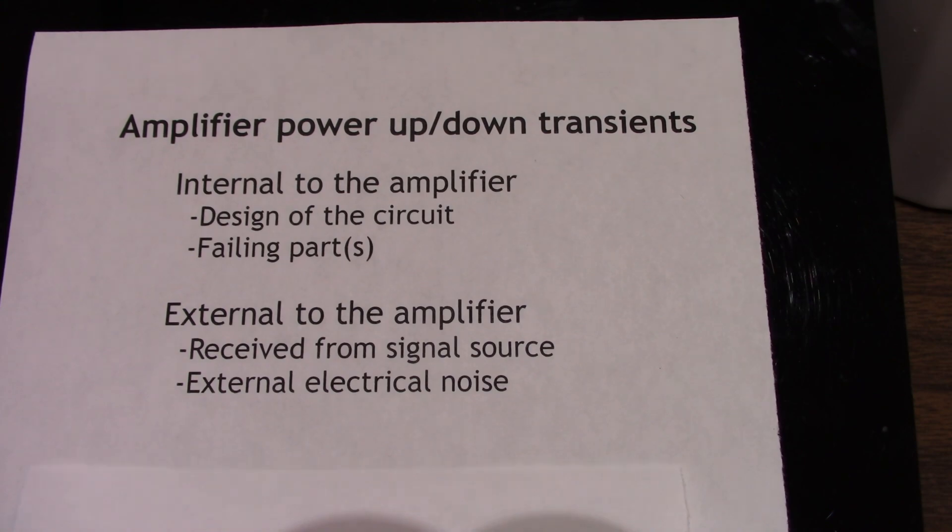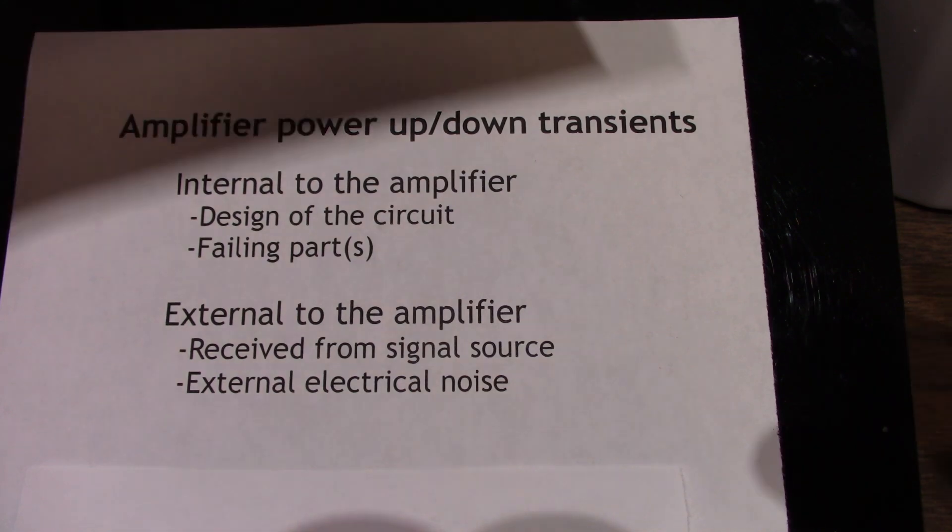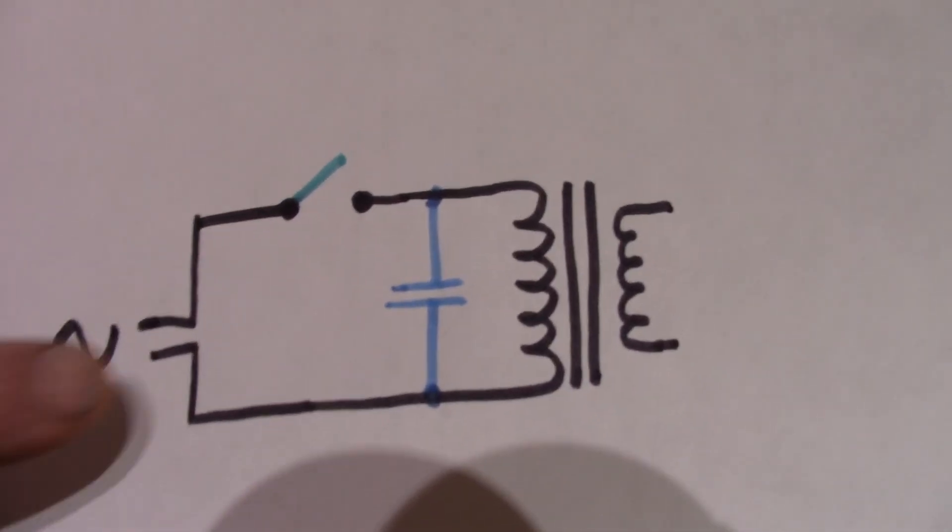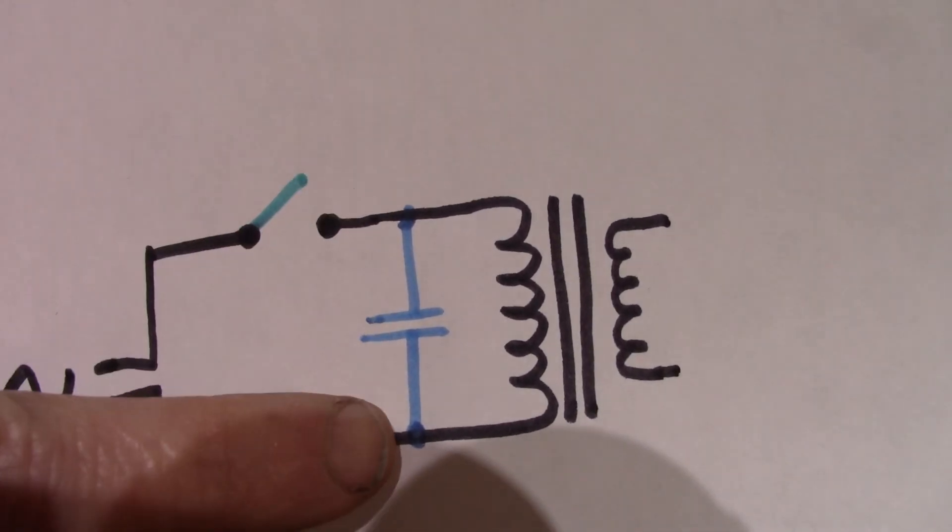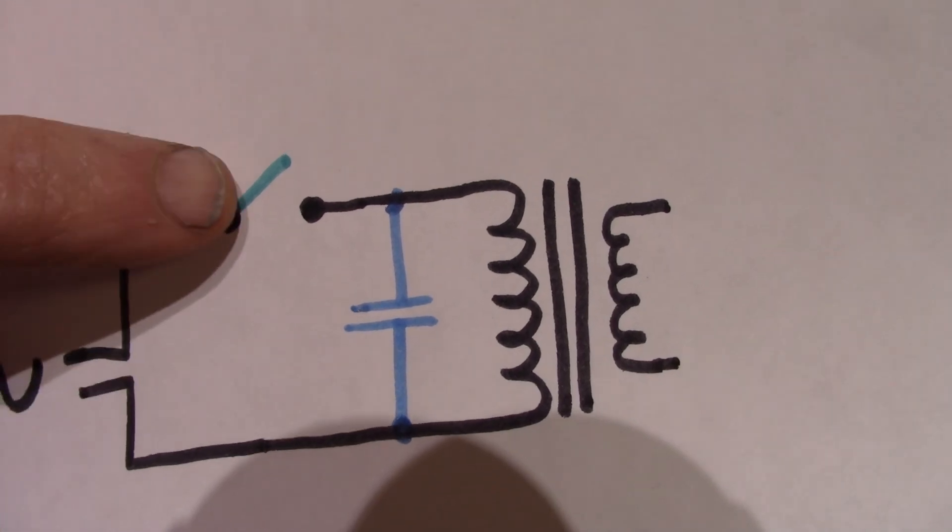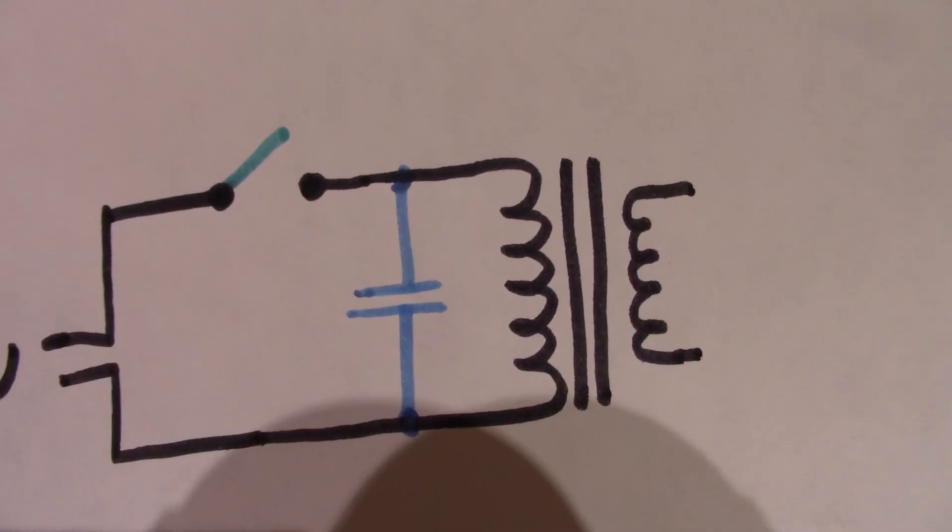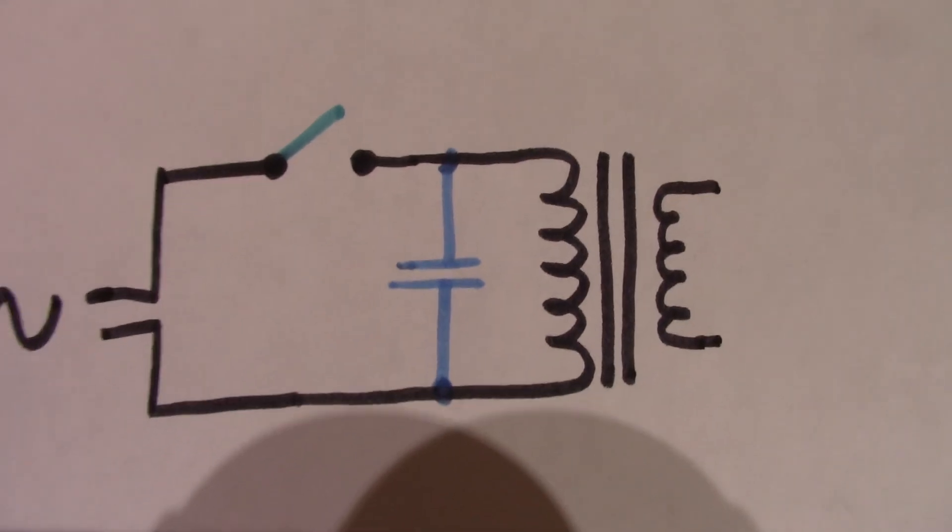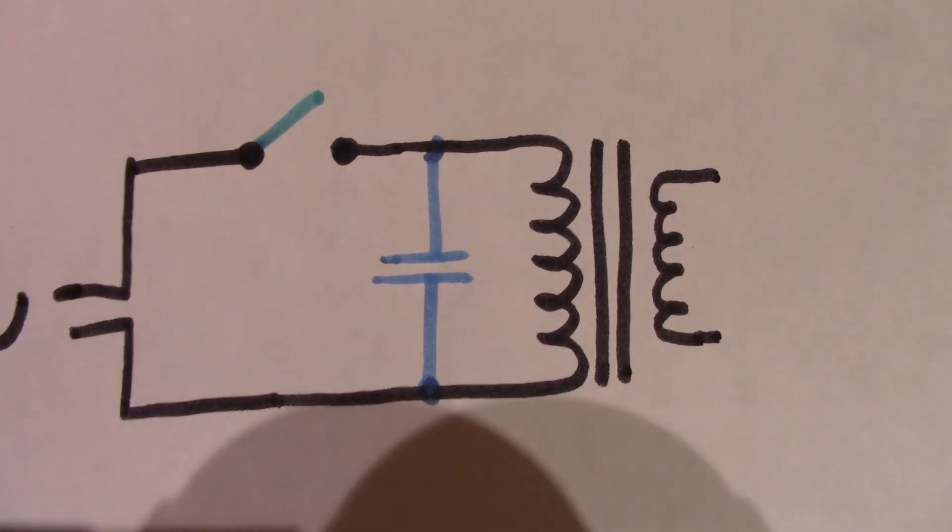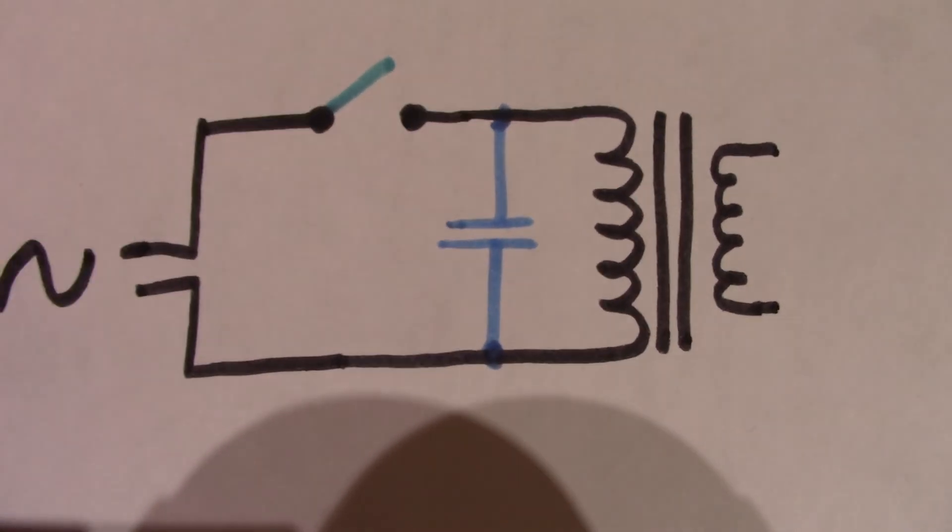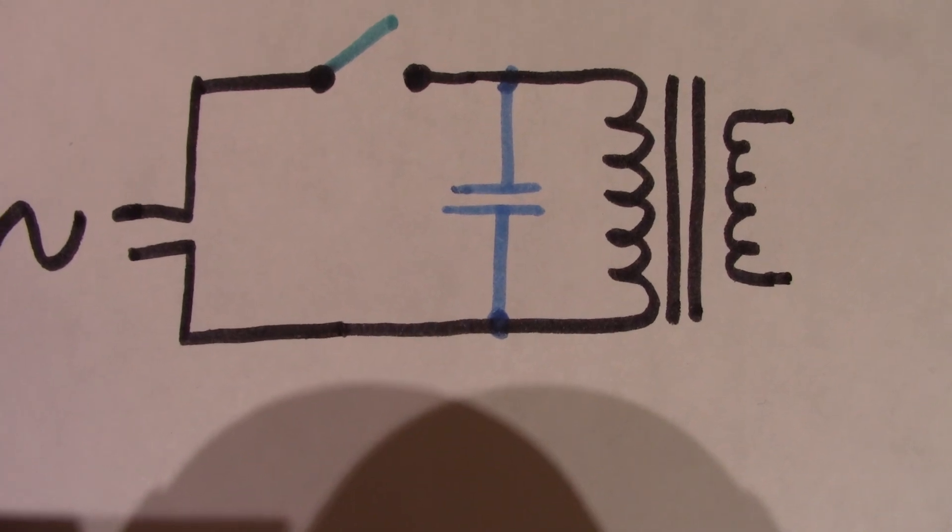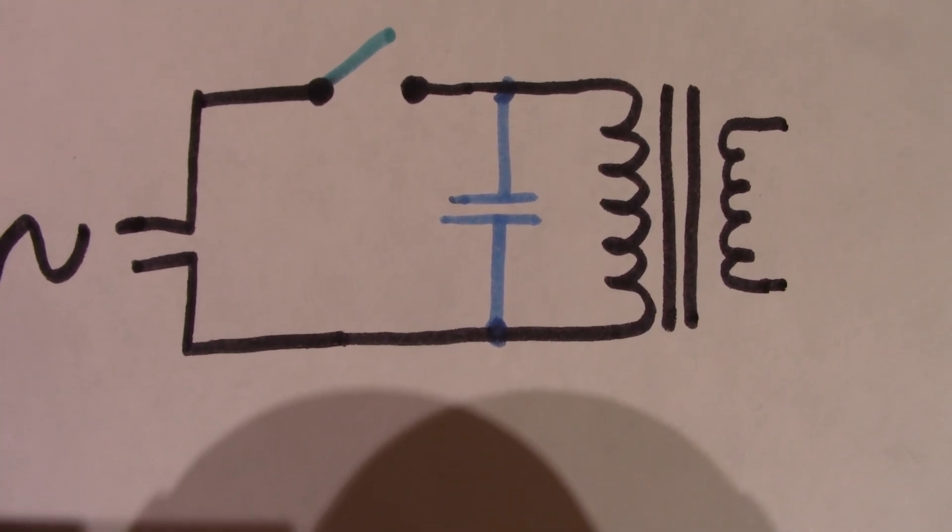Now, the transformer-operated device or even the amplifier itself should have some sort of a suppression device, and it could be as simple as an across-the-line capacitor. So when a switch is open, it helps absorb the noise created from the spark. And these capacitors are known to fail, so you might want to check those. A lot of devices don't include one, and you might want to put one in.